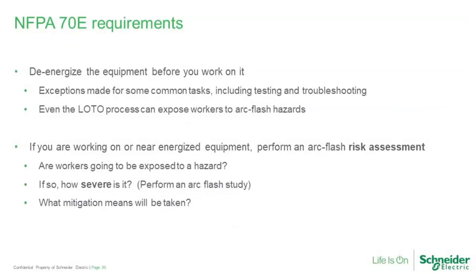Finally, NFPA 70E requirements, again the safe work practices. My summary, a very high-level summary: de-energize equipment before you work on it. And if we only did that, life would be very much more simple. But NFPA 70E makes some exceptions for some common tasks, including testing and troubleshooting. Even going through the lockout tagout process to de-energize equipment can potentially expose workers to arc flash hazards, because one of the things you're supposed to do during the lockout tagout process is test to verify that voltage has been removed. And so there's even potential exposure there.